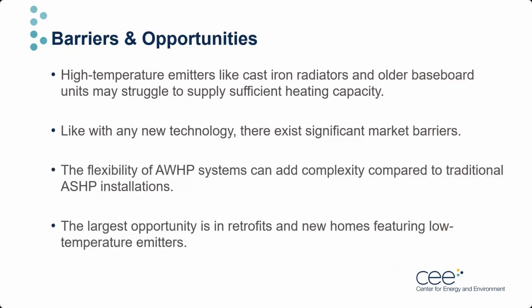Now let's go over some barriers and opportunities. As we mentioned at the top of the presentation, high-temperature emitters like cast-iron radiators and older baseboard units may struggle to supply sufficient heating capacity, especially in cold winter. More detailed load and design calculations are required in such retrofit scenarios to ensure that the air-to-water heat pump will still be able to provide the necessary heating load with lower supply temperatures.